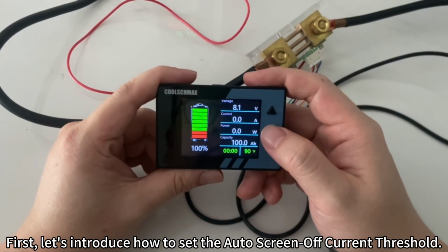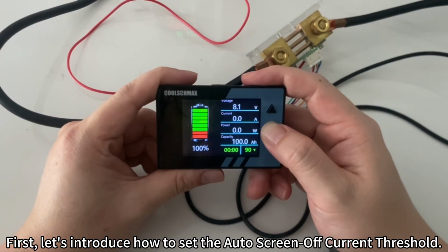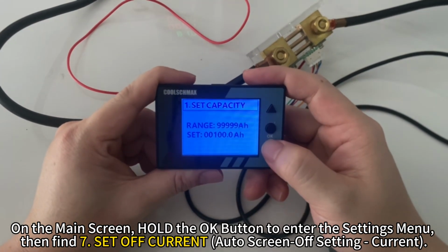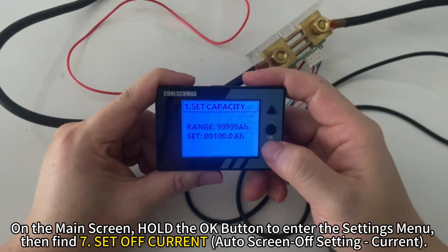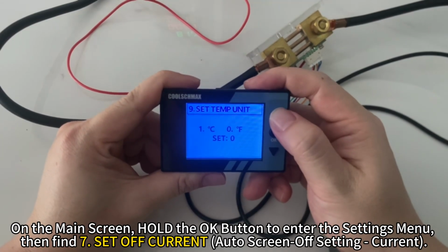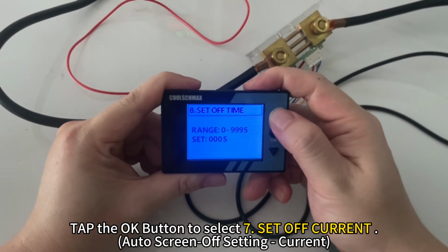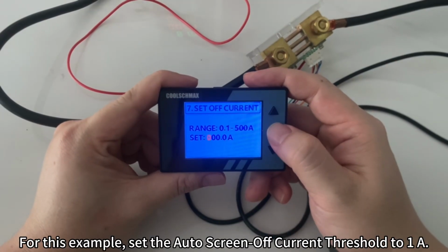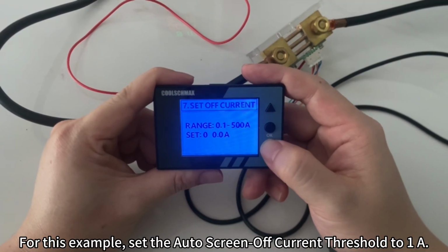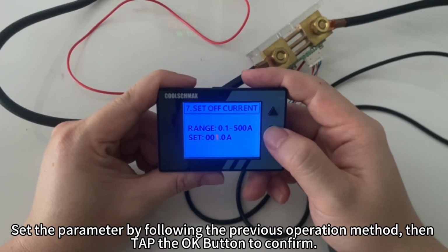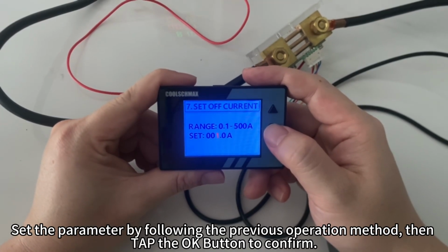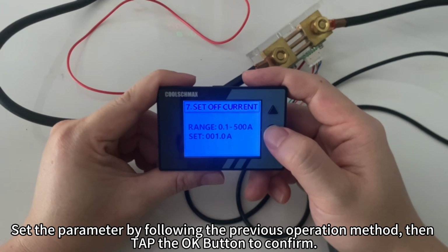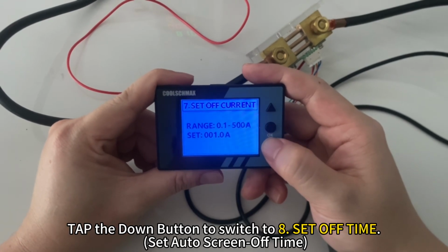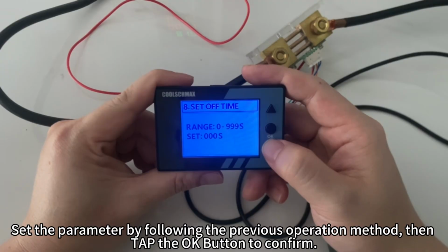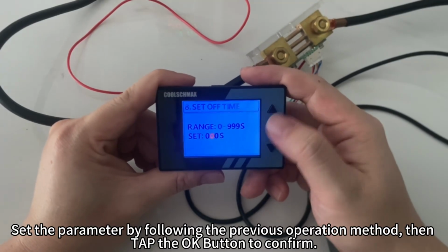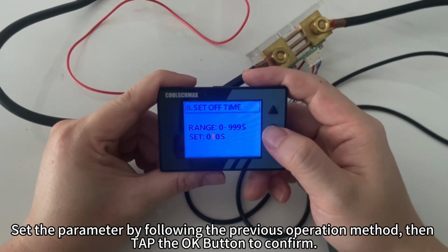First, let's introduce how to set the auto screen off current threshold. On the main screen, hold the OK button to enter the settings menu, then find 7, Set Off Current. Tap the OK button to select 7, Set Off Current. For this example, set the auto screen off current threshold to 1A. Set the parameter by following the previous operation method, then tap the OK button to confirm. Tap the down button to switch to 8, Set Off Time. Set the parameter by following the previous operation method, then tap the OK button to confirm.